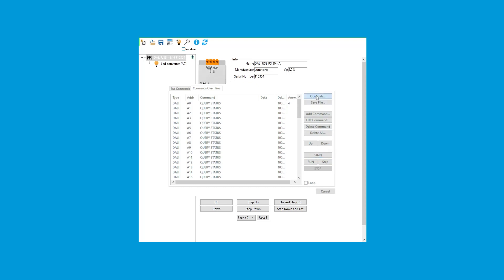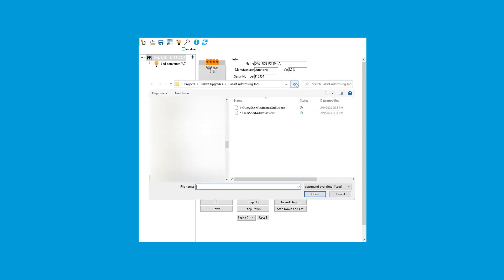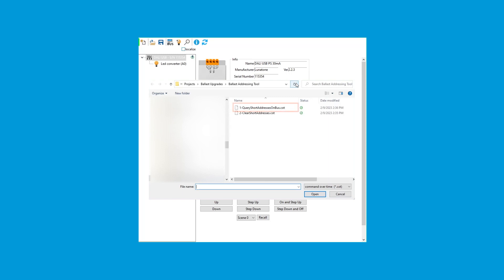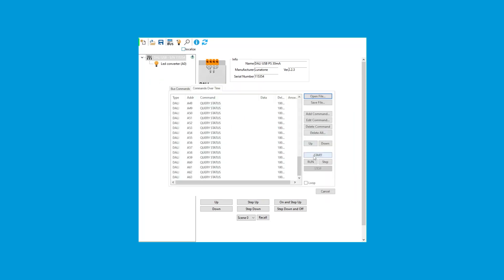Once you've verified that, click the Open File button and choose the Clear Short Addresses command. Now click the Start button. This process actually clears the address in the device. To verify that it's been cleared, click Open File again and choose the Query Short Address on Bus command again, then click Start.